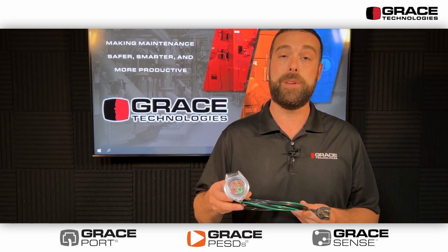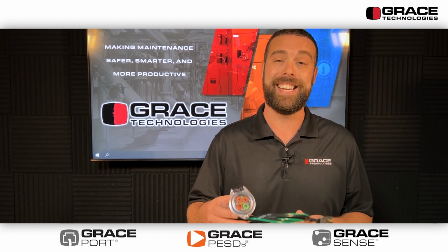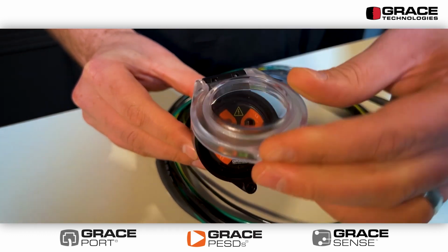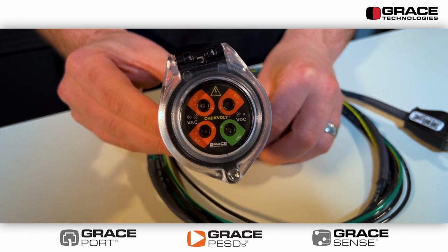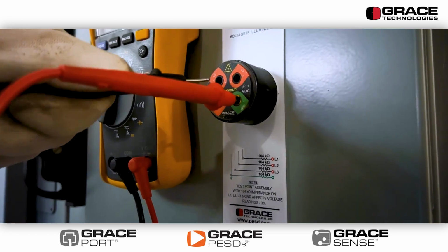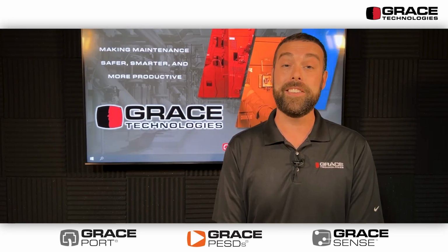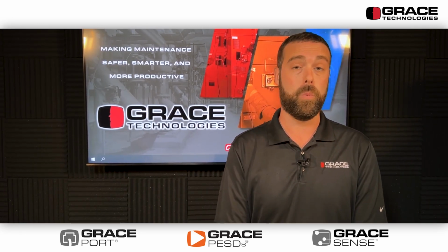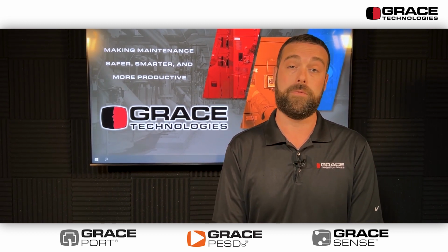This device can be wired into industrial applications up to 1,000 volts AC and DC. The way that this device is installed, customers would use a simple 30 millimeter push button knockout and then wire the 14 gauge 4-wire terminations in parallel to the source voltage. The great thing about the new CheckVolt device is that it does comply with NFPA 70E standard, specifically Article 120.5, for the process for establishing an electrically safe working condition.